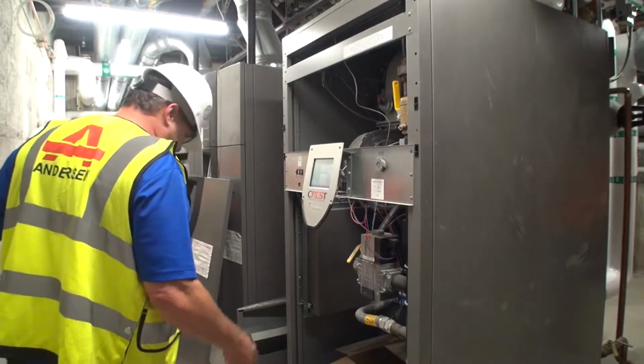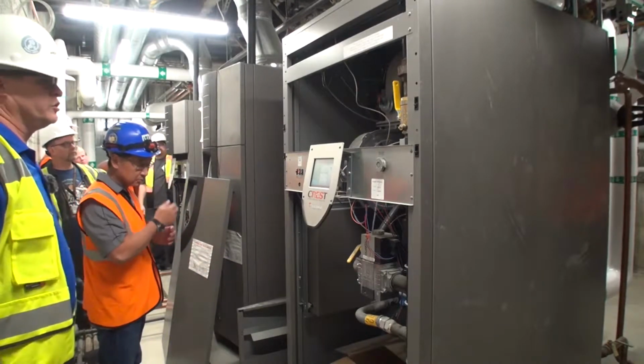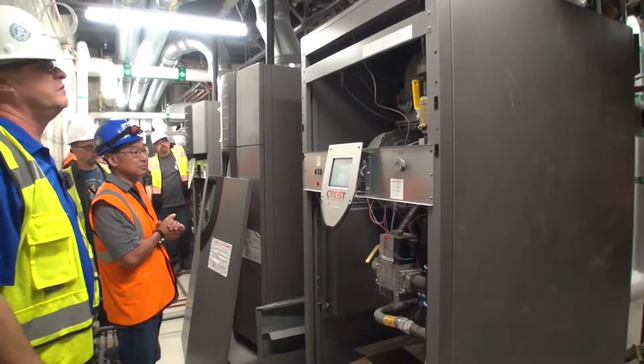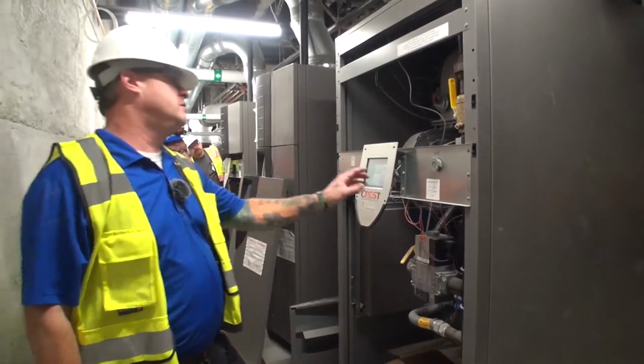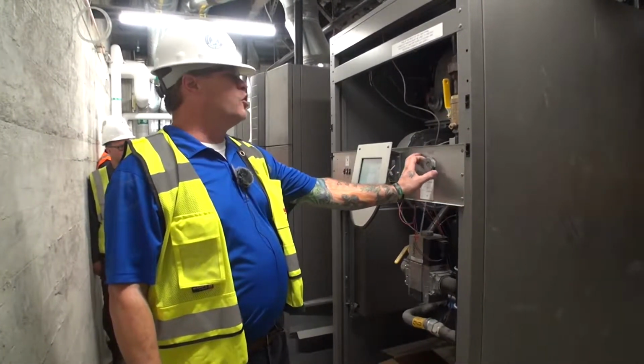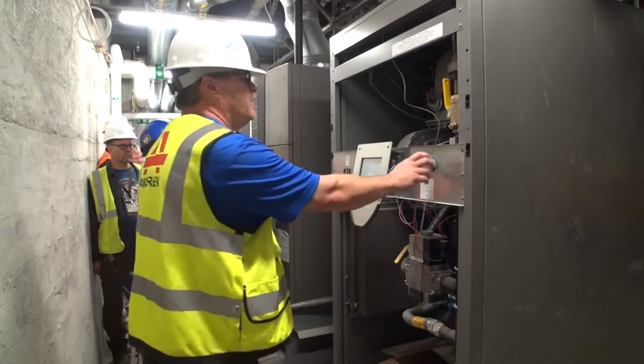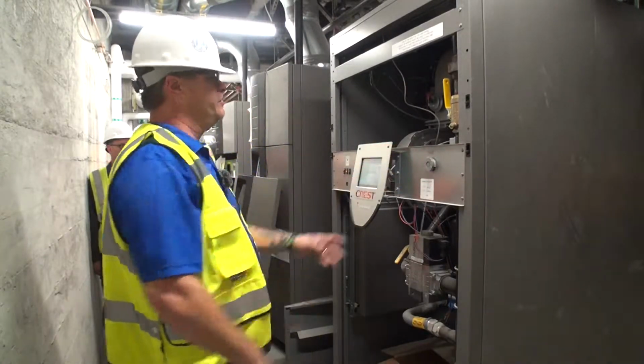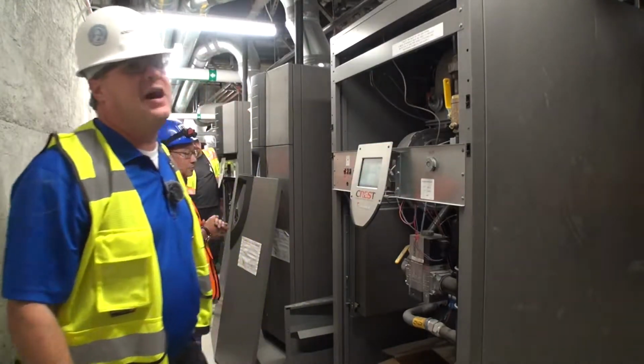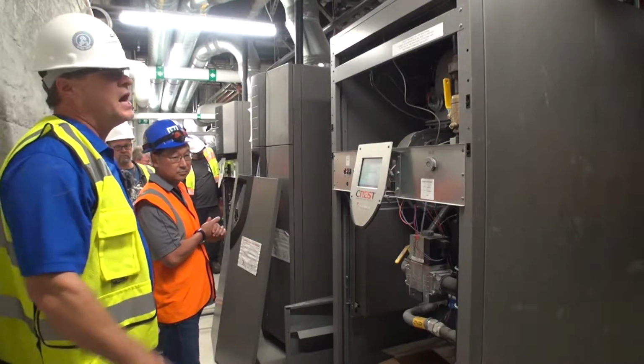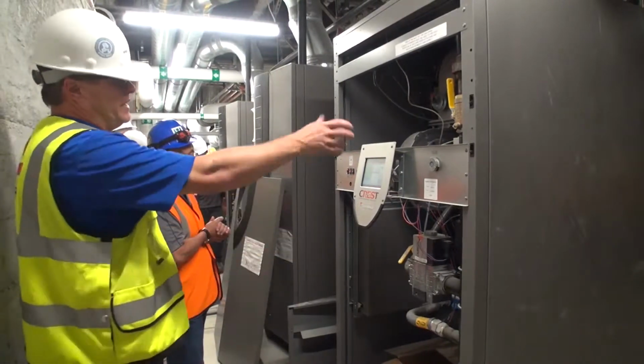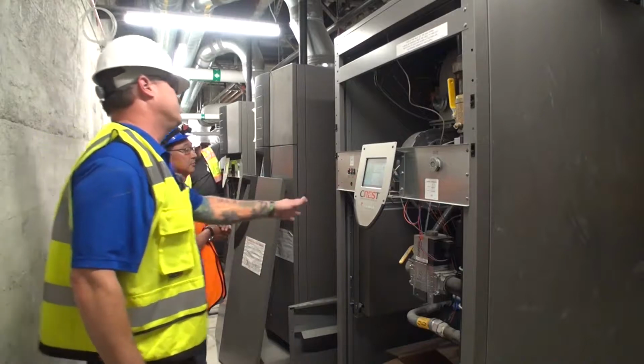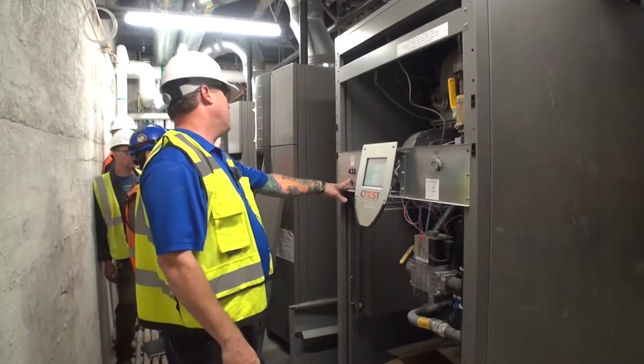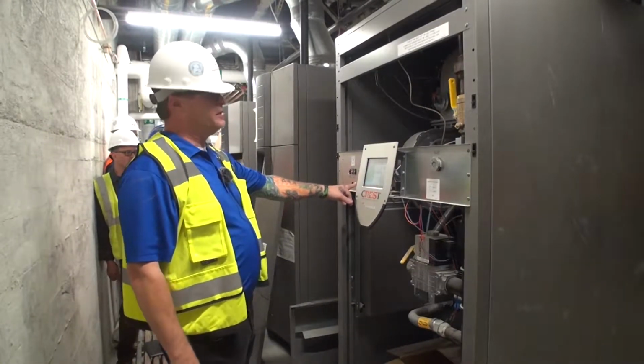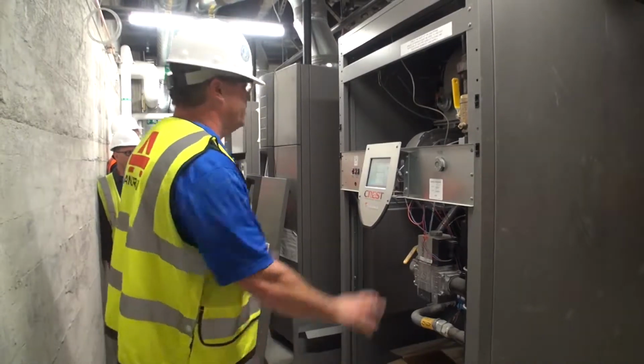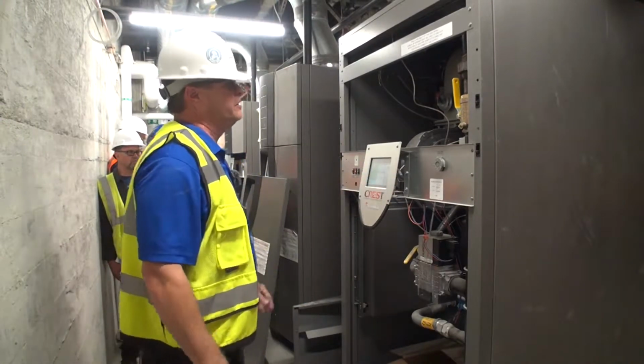I'll let Sheldon take over in the sense of controls because there's really not too much here. The only thing, well, here's your high limit control in the sense of safety, that could be dialed in. Usually we set them about 195, and that's what the high limit is set at. That's adjustable. And then also on the front of the board, here's your main power, reset, and your test buttons. Other than that, that's the touch screen display.